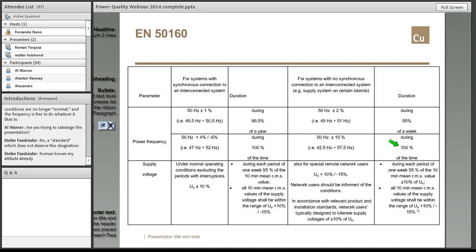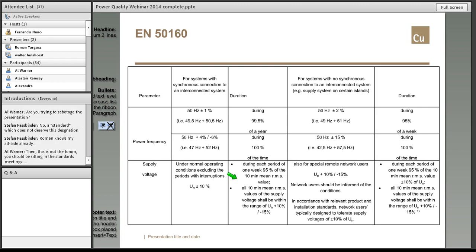non-synchronous systems. And this is for synchronous system for supply voltage. So this is plus minus 10% for 95% of 10 minutes root mean square value. While for plus 10 and minus 15, 100% of the time, this condition of plus 10, minus 15 should be fulfilled. And we've got here the conditions for asynchronous network.